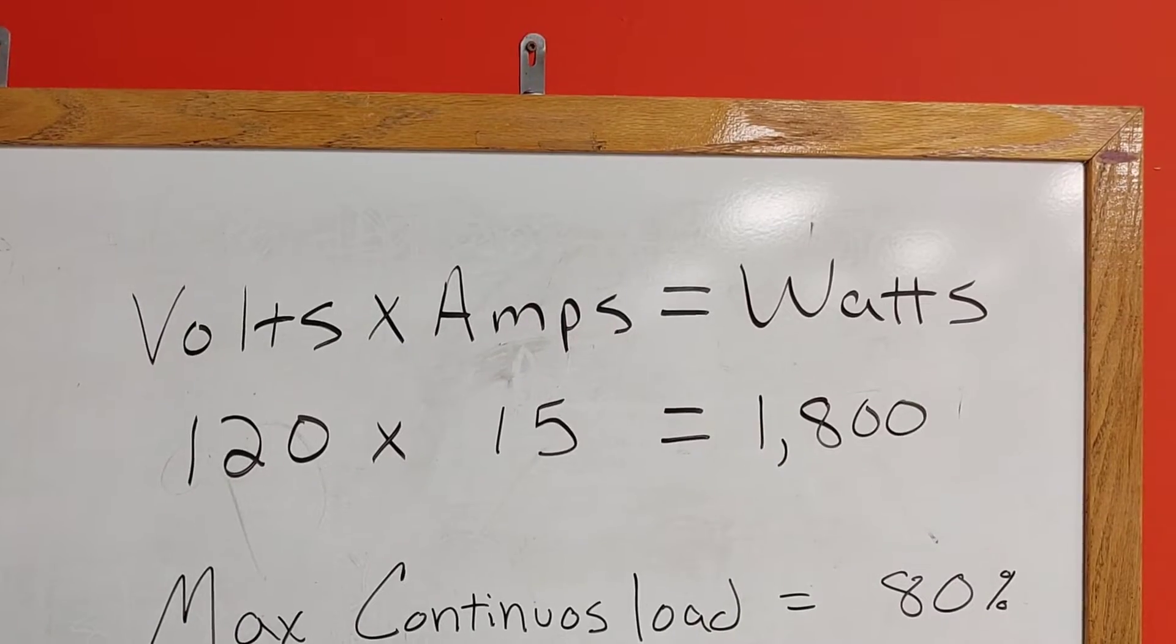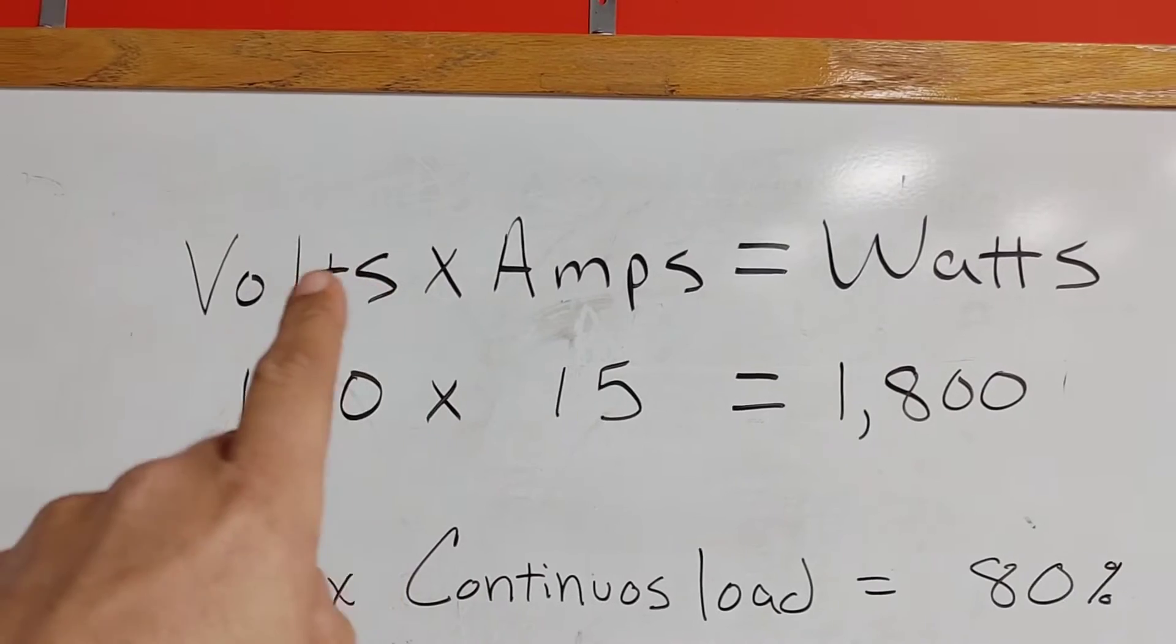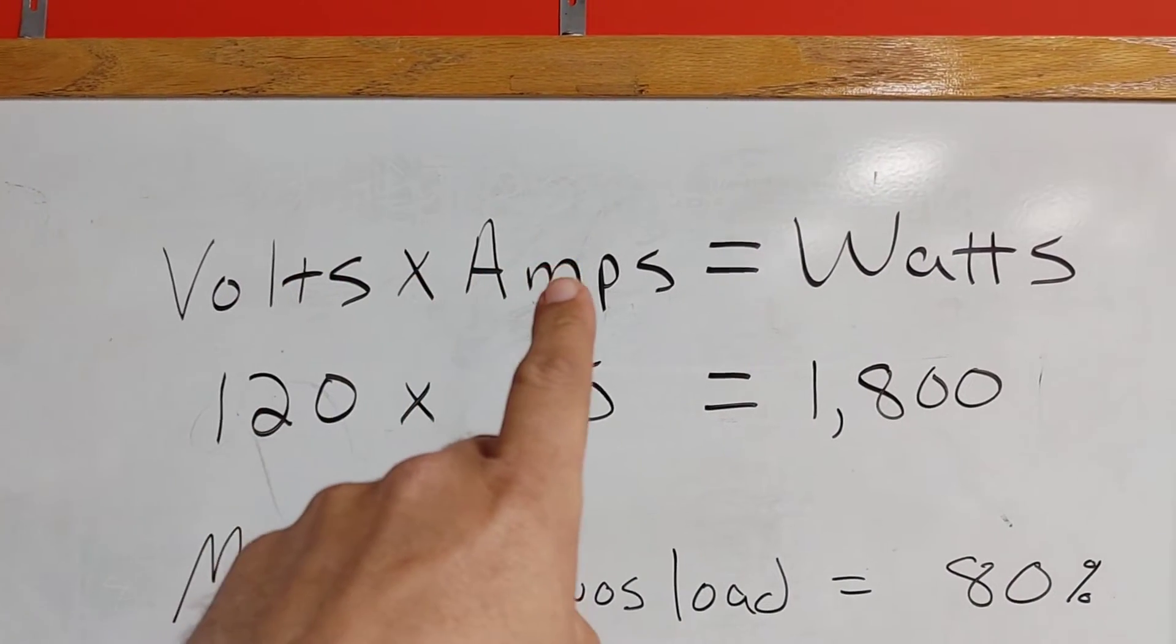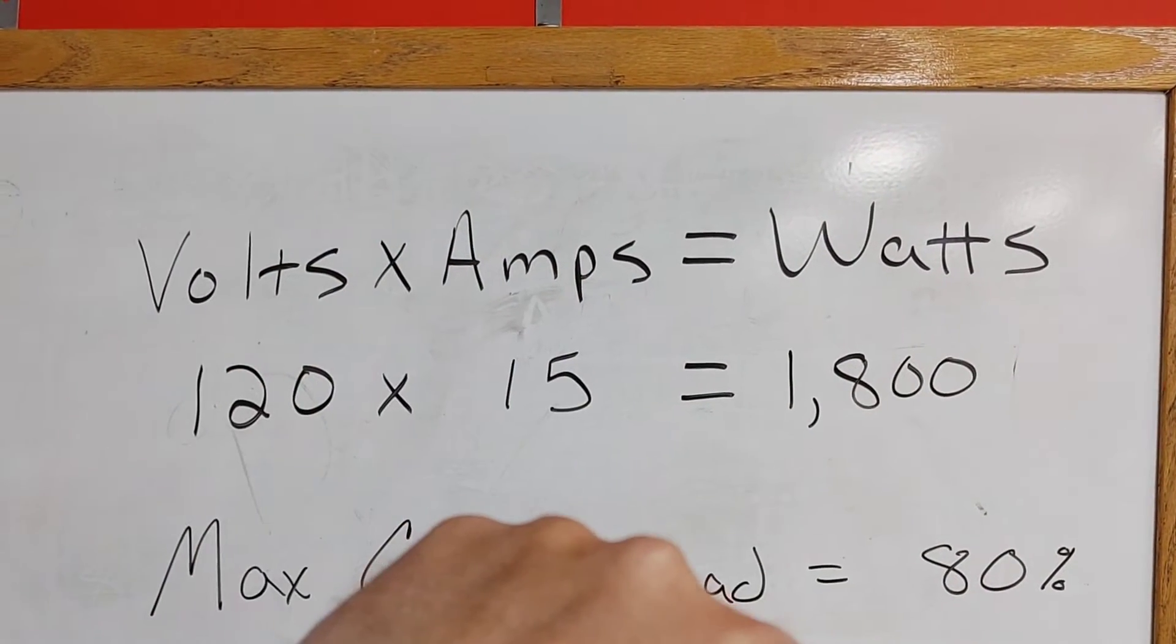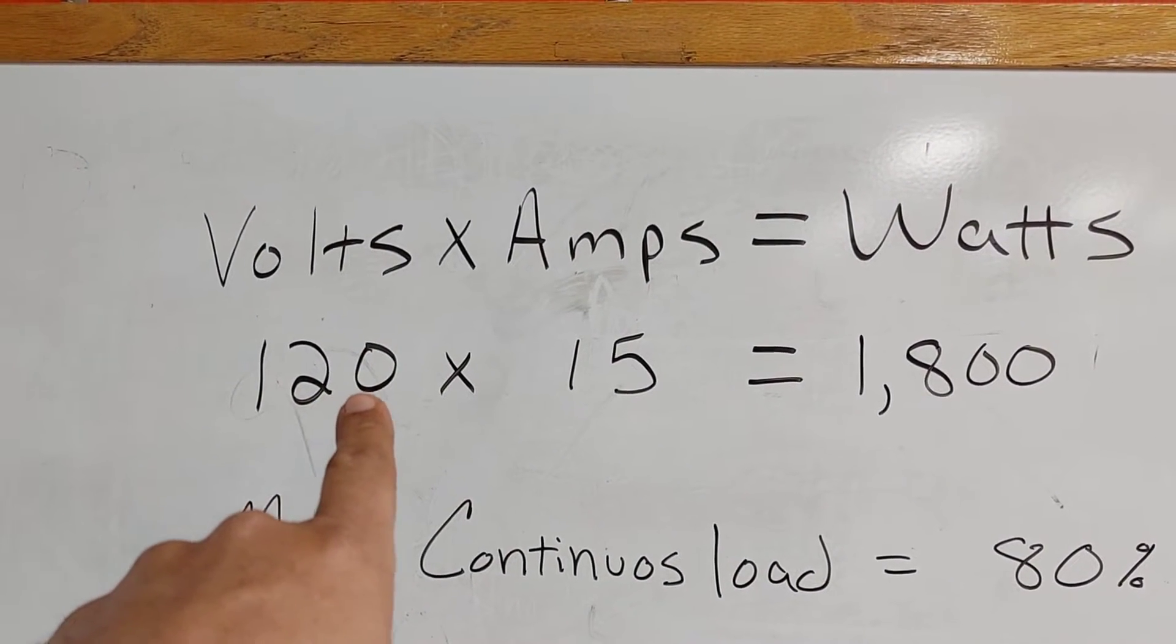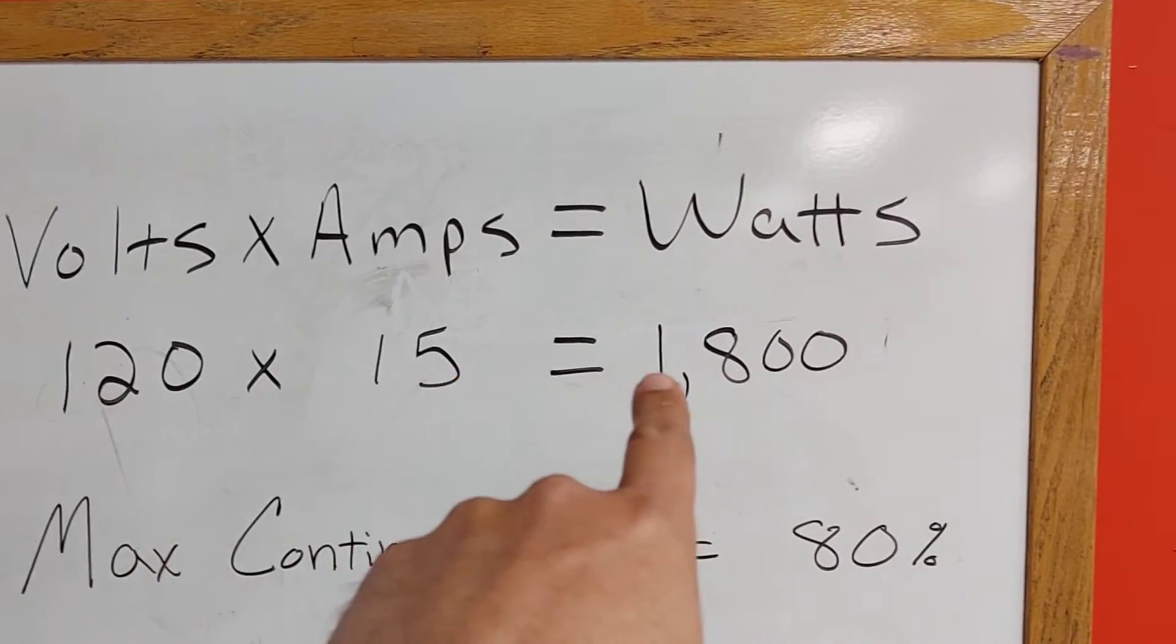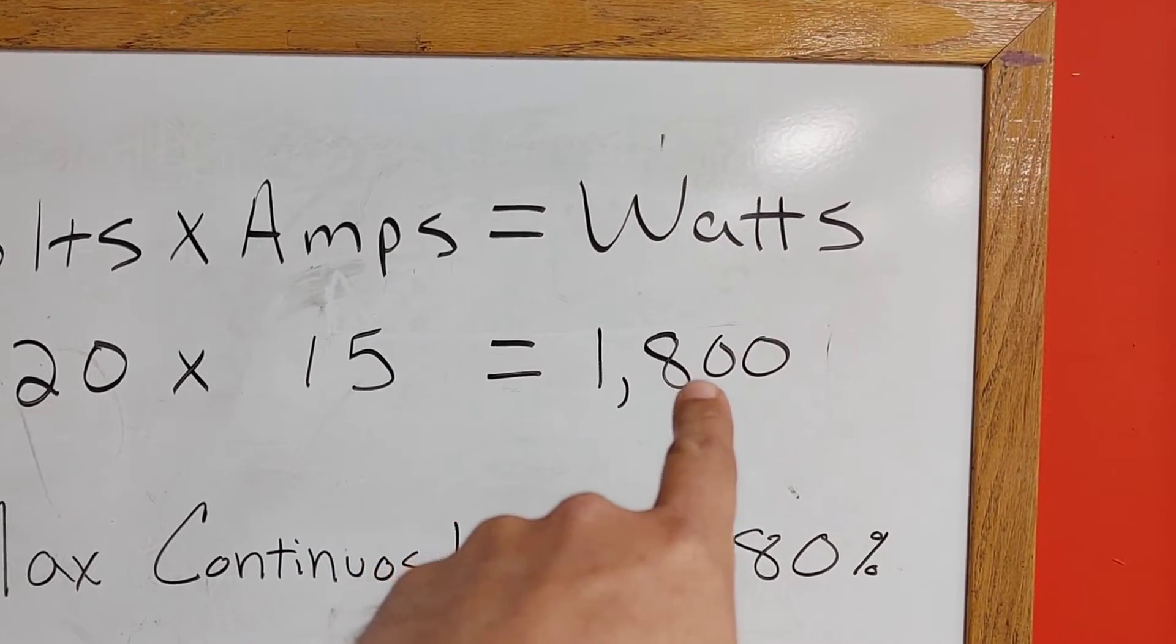To figure this out, we need to know a little bit of Ohm's Law. Let's take a look at the dry erase board. The first bit of Ohm's Law we need to know is how to figure out watts, and how we figure that out is you take your volts times your amps. In the situation I want to discuss, we're going to be on a 120 volt circuit. We're going to be using a 15 amp breaker, and that equals 1,800 watts.